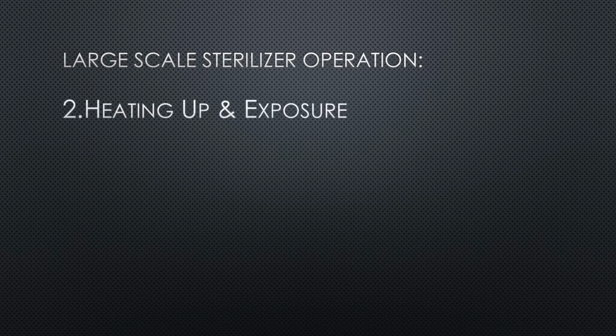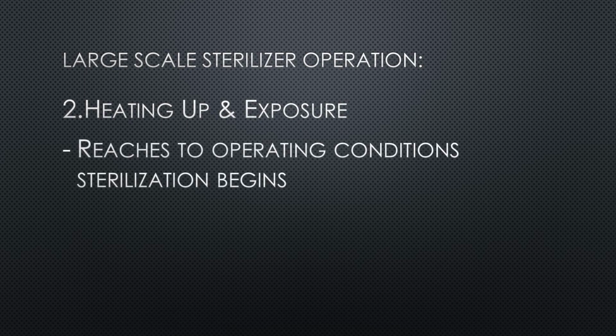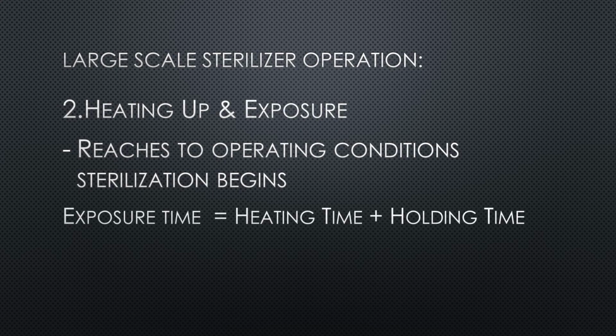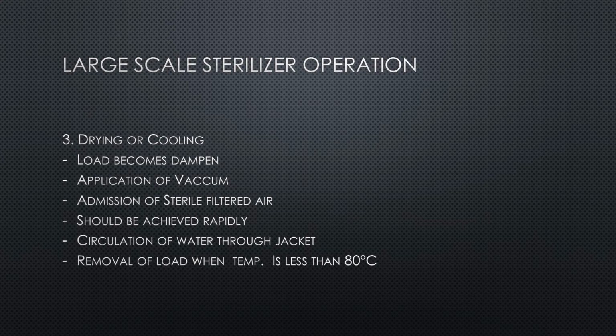Now the second step is heating up and exposure. Here, when the sterilizer reaches its operating temperature and pressure, the sterilization stage begins. The exposure time we have to maintain is nothing but the heating time, and whatever time the articles are held inside, that total timing will be called the exposure time. The third stage is cooling and drying.